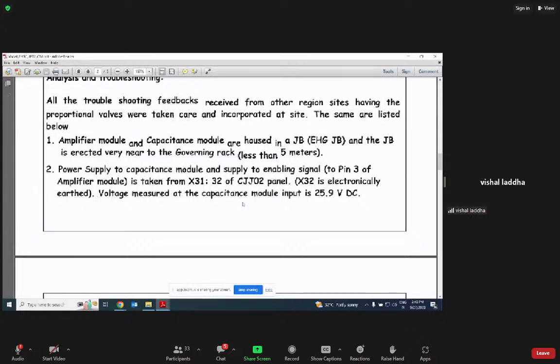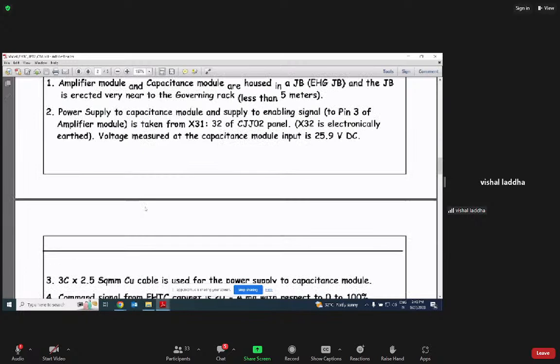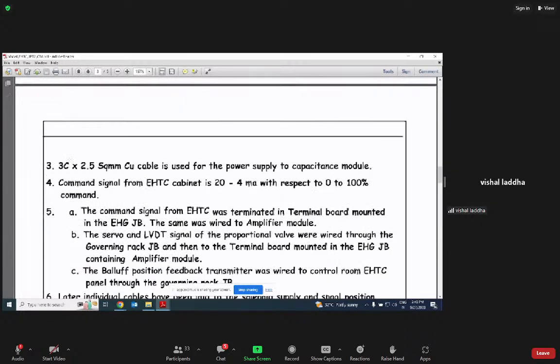That is a very critical point. Electronically earthed. If it is not earthed, then hunting can be observed. Voltage measured at the capacitance module is also 25.9. The third thing to be taken care of: three core 2.5 square copper cable is used for power supply, and it is isolated from the signal cable. Command signal from the EHTC cabinet is 20 to 4 mA with respect to 0 to 100% command.